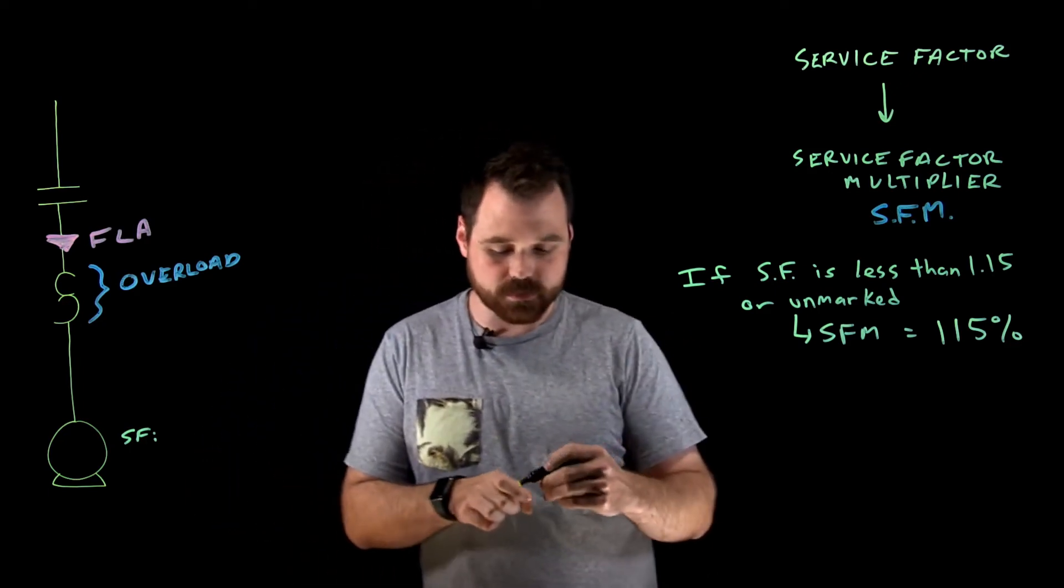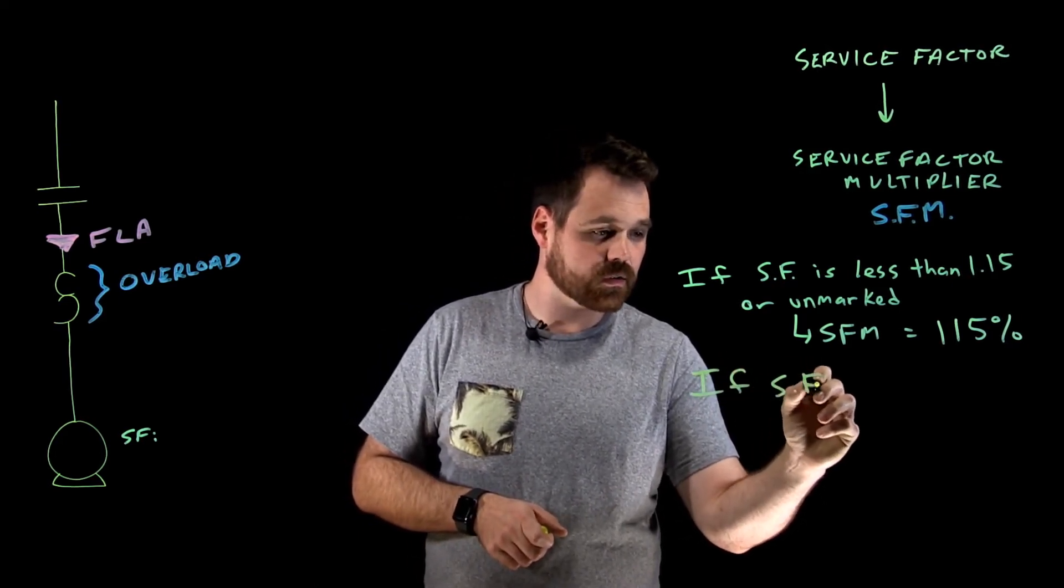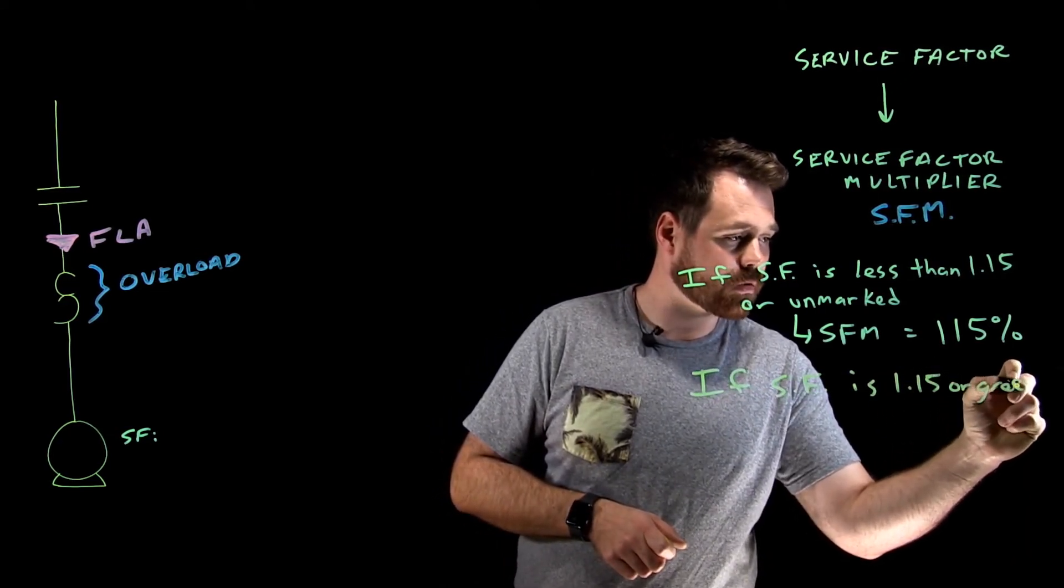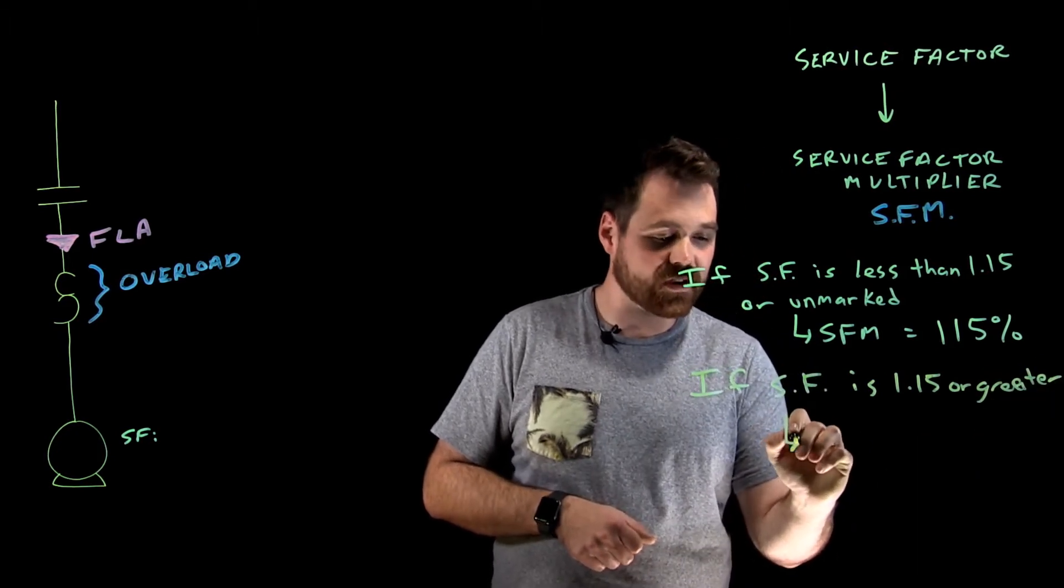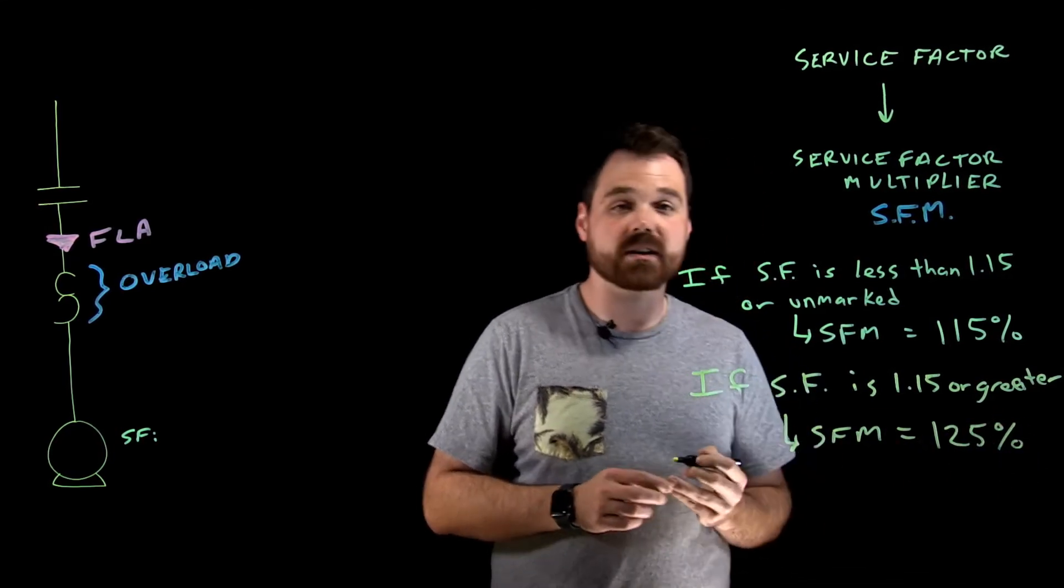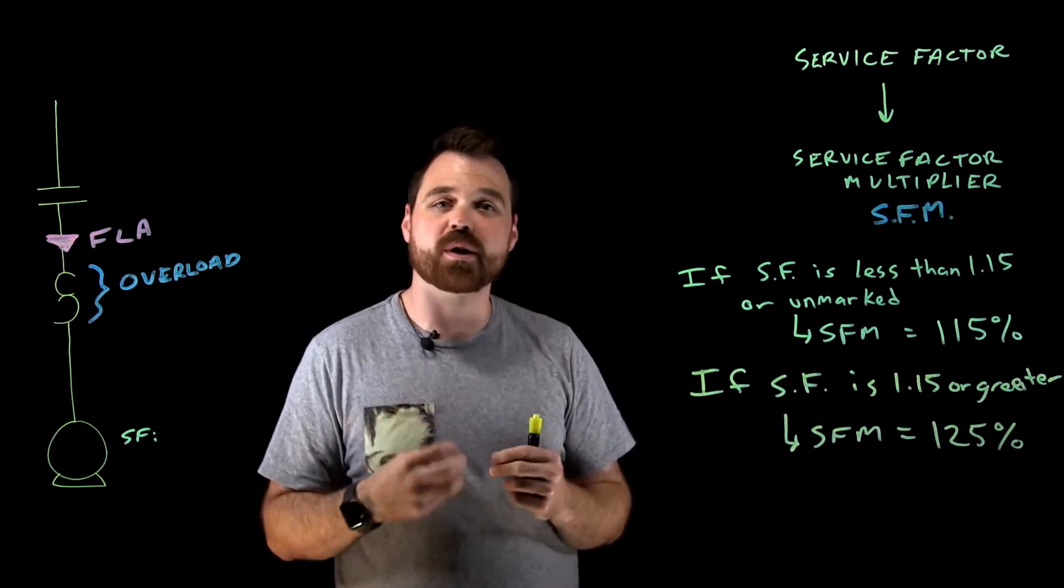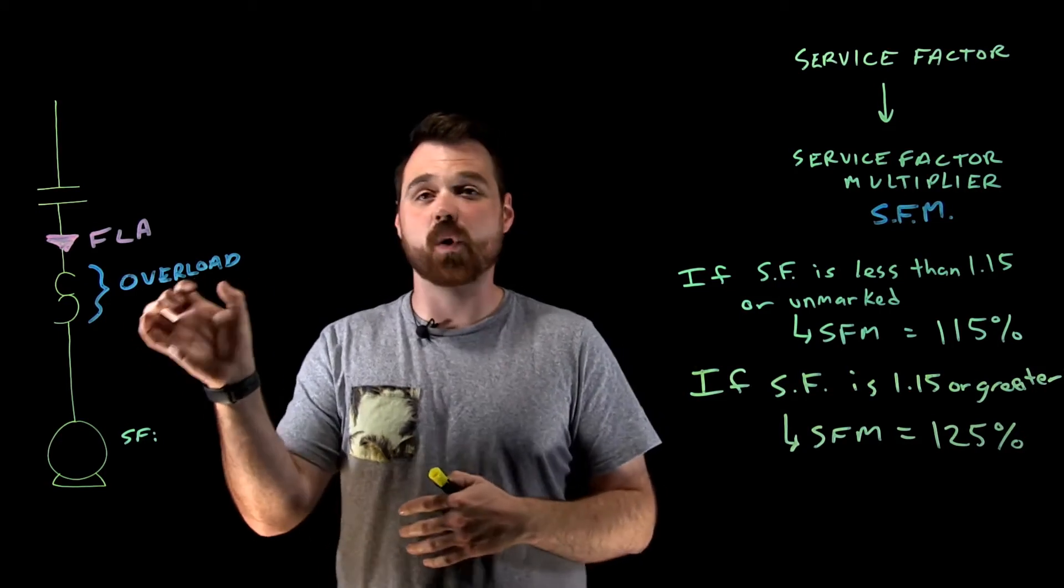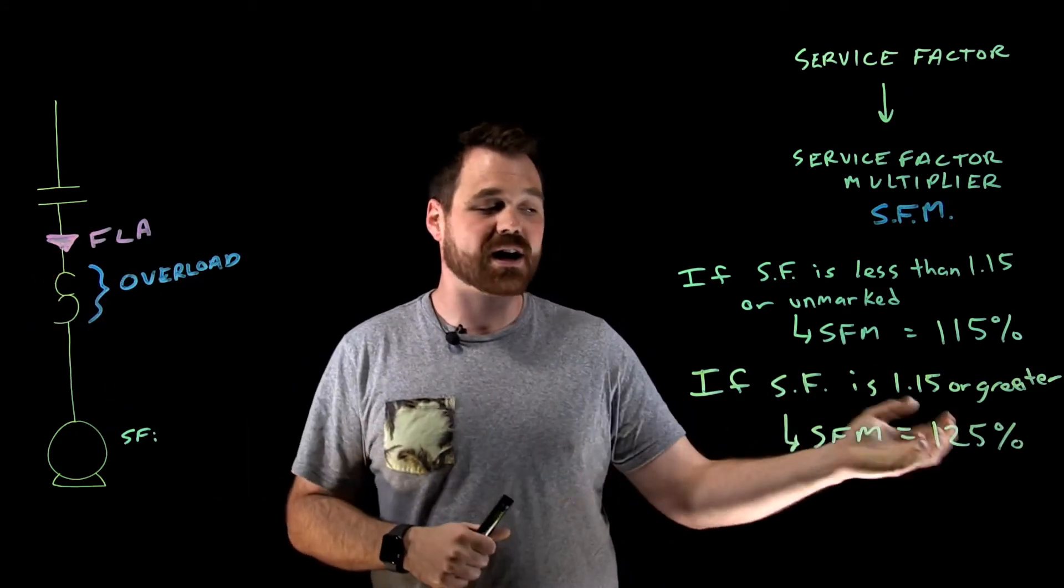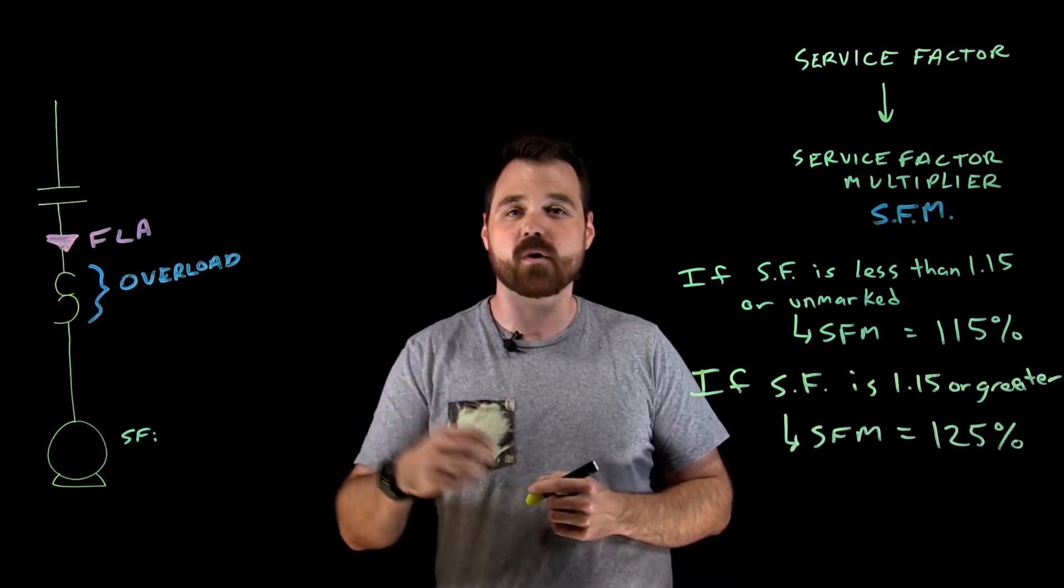Now, if different one here, if your service factor is 1.15 or greater, then your service factor multiplier equals 125%. So if my motor has a stamped service factor of 1.15 or anywhere above 1.15, then to size this overload setting, what I would do is I would take my FLA or the current flowing through that overload, and I would times it by 125%. That would be my maximum allowable setting of overloads.